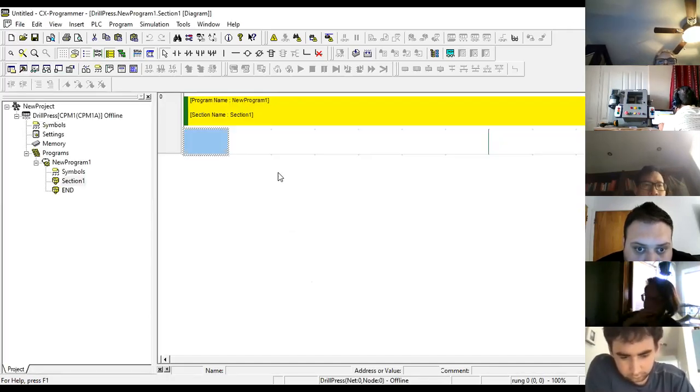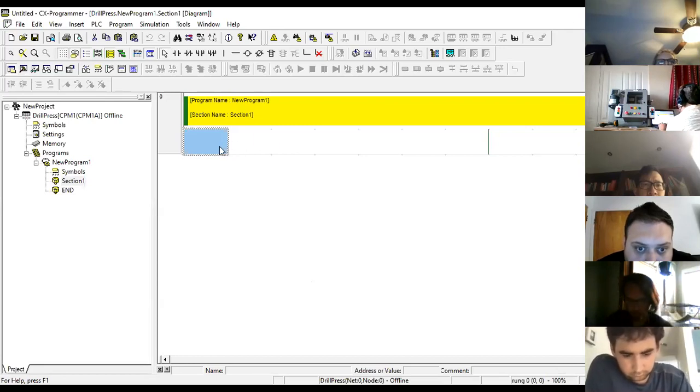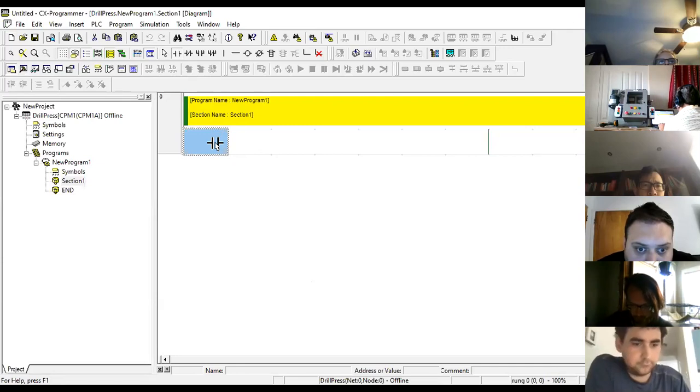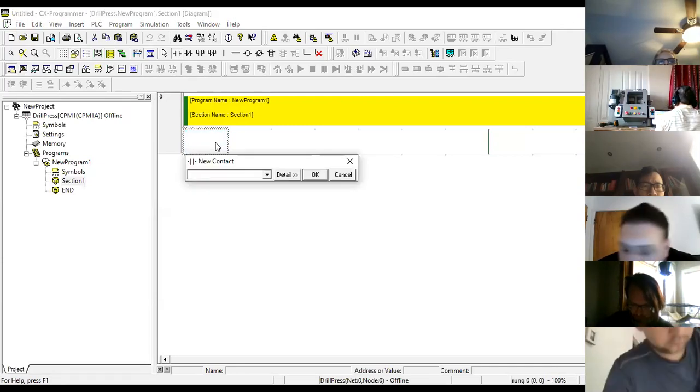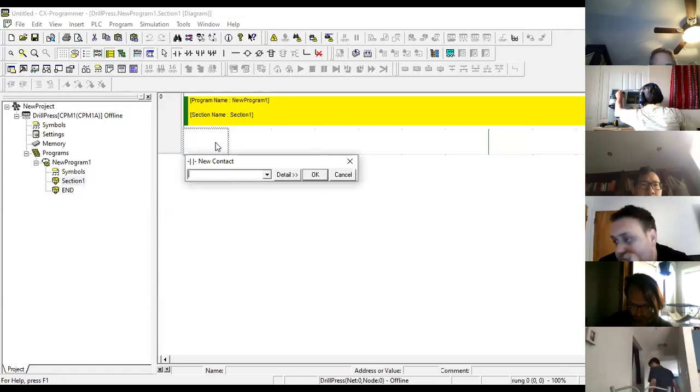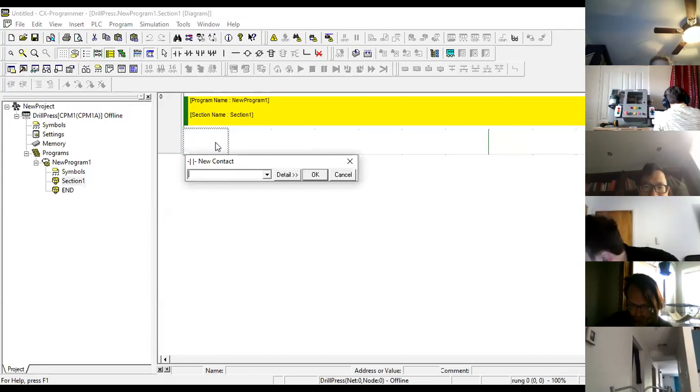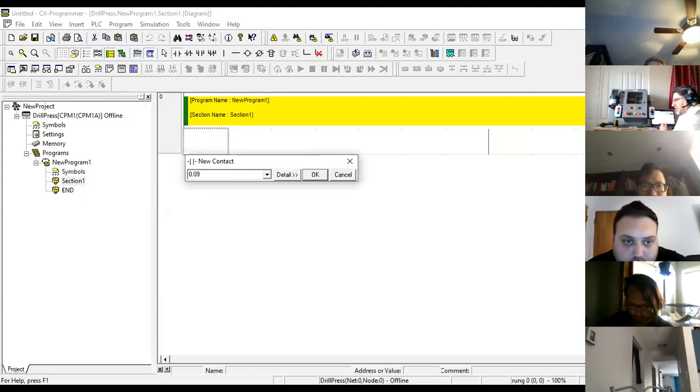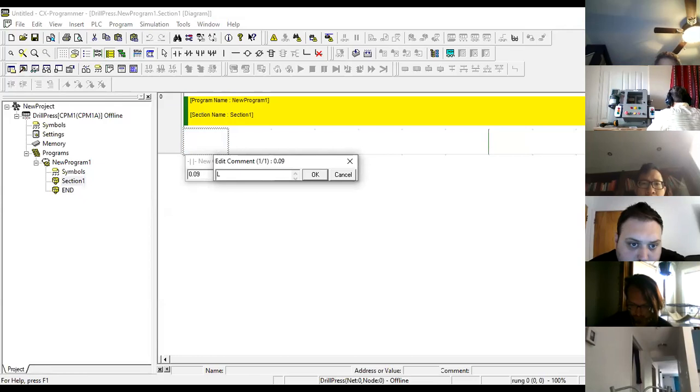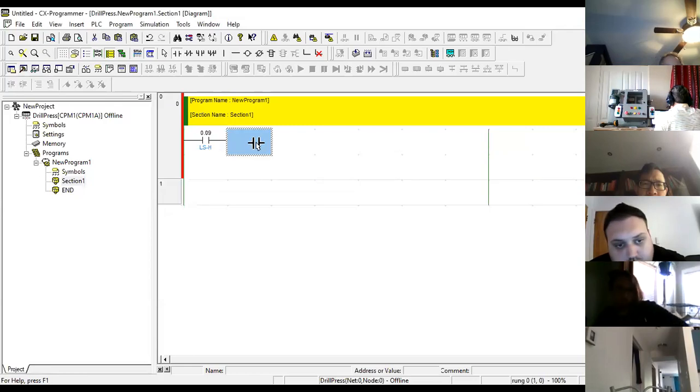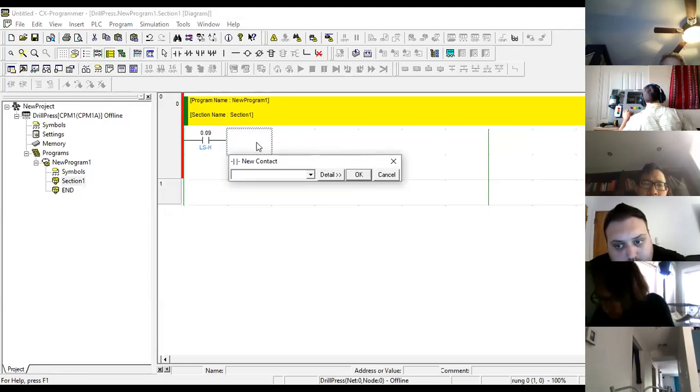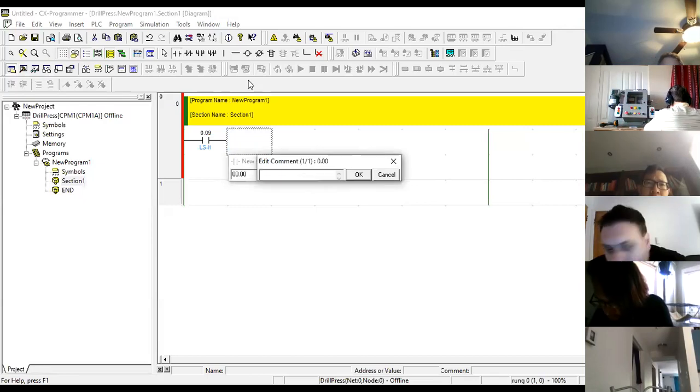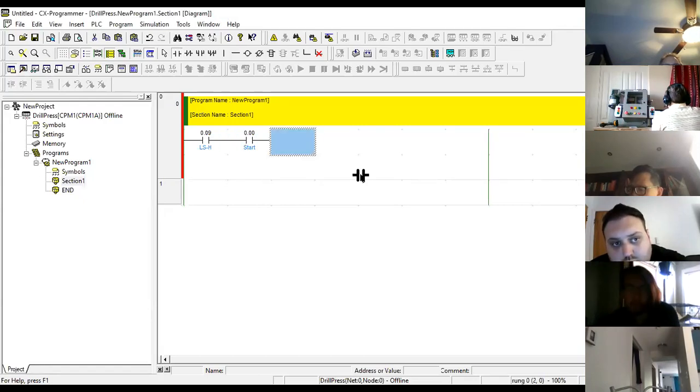So now what I want to do is I want to put in my contact. I'm going to start with a normally open contact here. This normally open contact was the limit switch. If I look at the address in my PLC right now, I have 09, so 0.09. It's going to prompt me for a name, so I'm going to put down limit switch high. Here I'm going to put the start push button, my 00.00, which is my start.